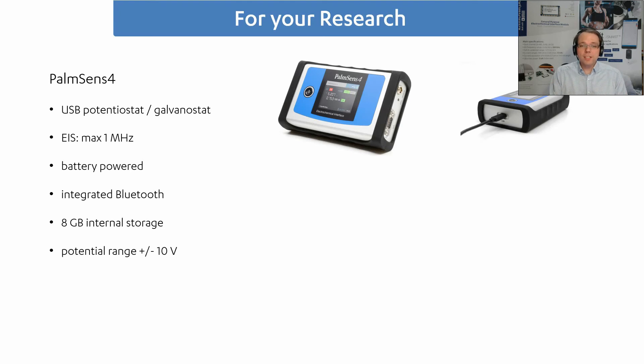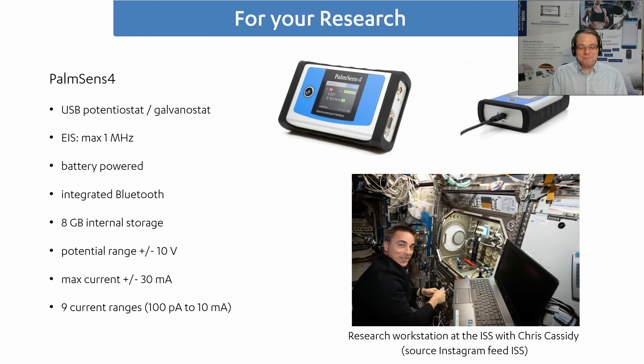The potential range is up to 10 volts and the maximum current is 30 milliampere. We can also go down into the picoampere range because we have a lot of current ranges. Something quite exciting happened for us last year — our PalmSens4 made it to the International Space Station. You can see Chris Cassidy on a research station in the ISS with a PalmSens4.